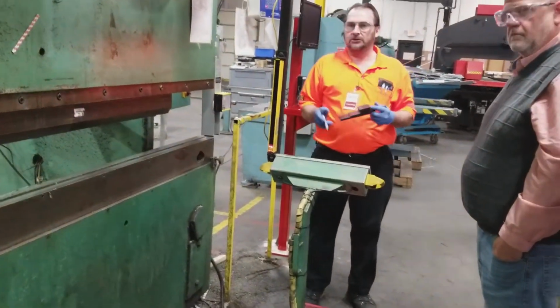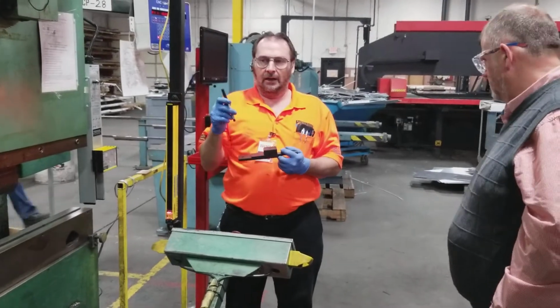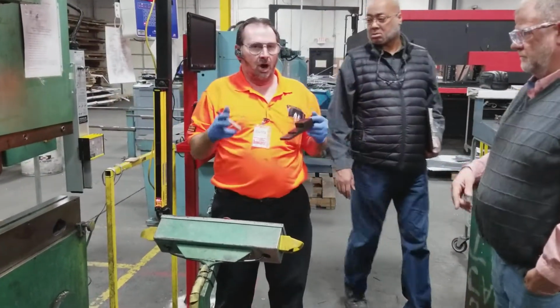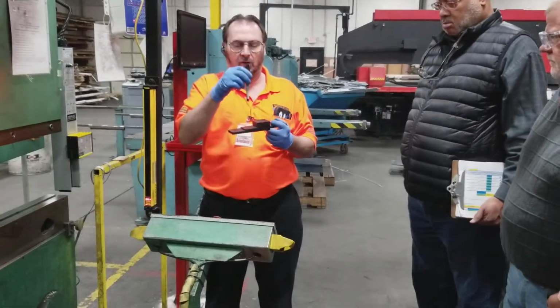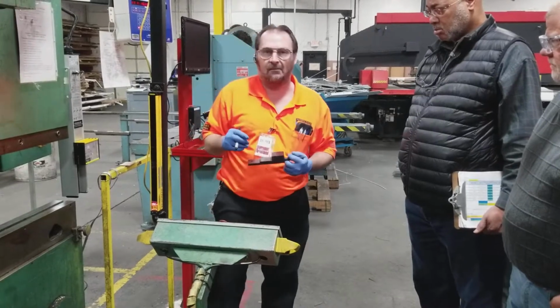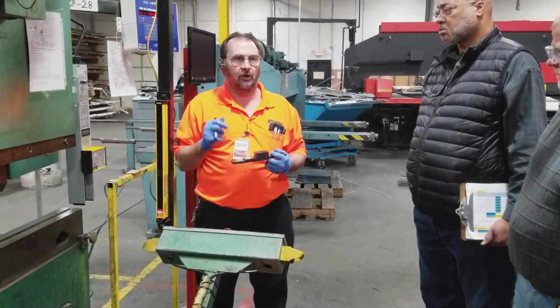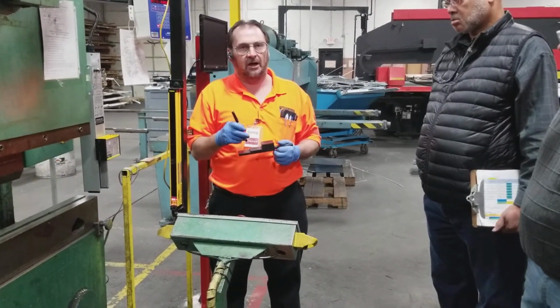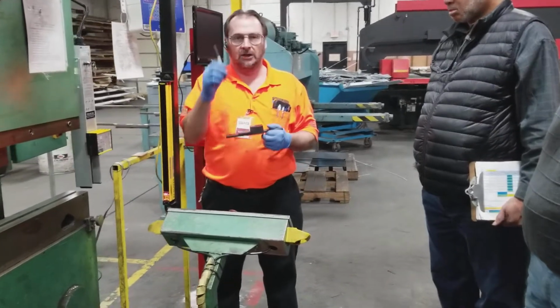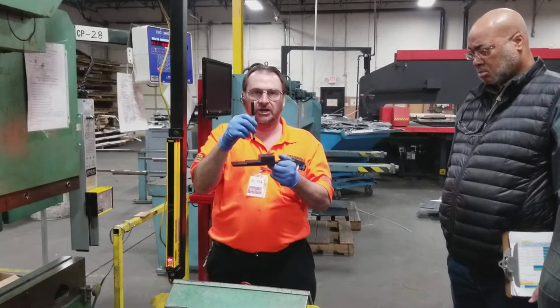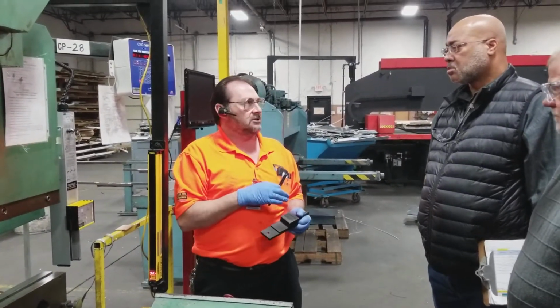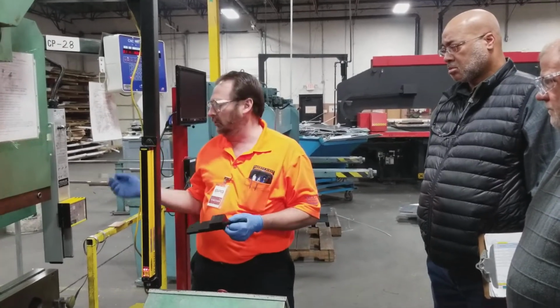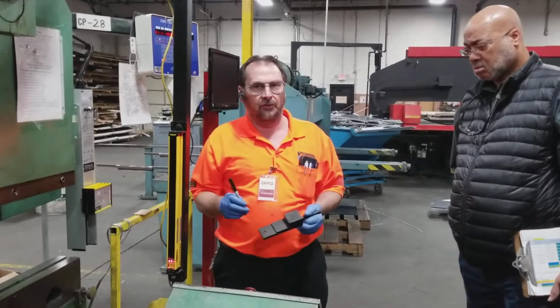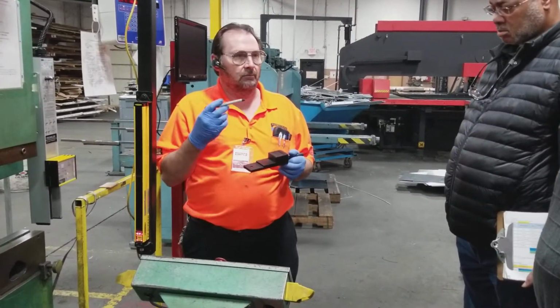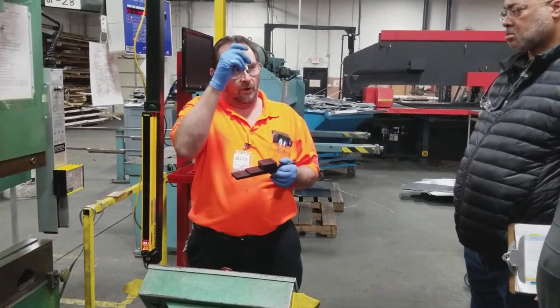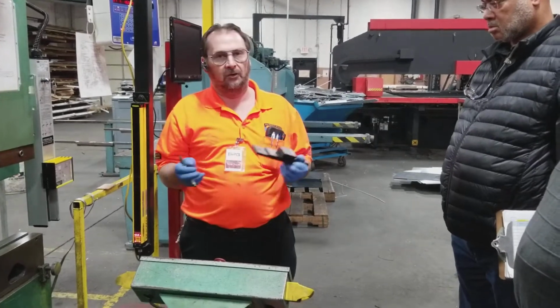The way this system operates is as the ram is coming down, the laser is actually monitoring the movement of the ram. When it sees the ram go into a transition of slow speed, it starts a timer. Those timers time out at 7/10 of a second, very quickly. Once it times out, it will do a distance check of 4 millimeters. So you're doing a timing sequence, then a distance check. If there's no obstruction during that timing sequence and/or distance check, the system will mute out. You'll get a muting signal, and it'll allow you to go right on through the part. If there's an obstruction before either of those two complete, it will come down and stop, or come down and stop and go back up, depending on the machine.